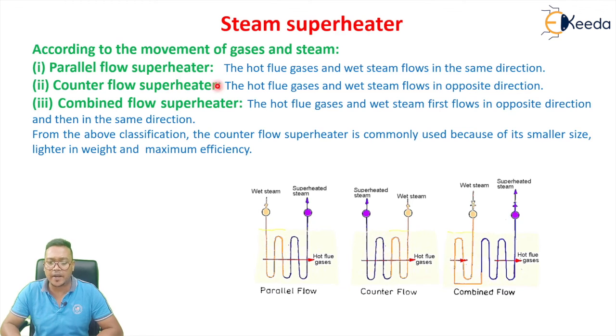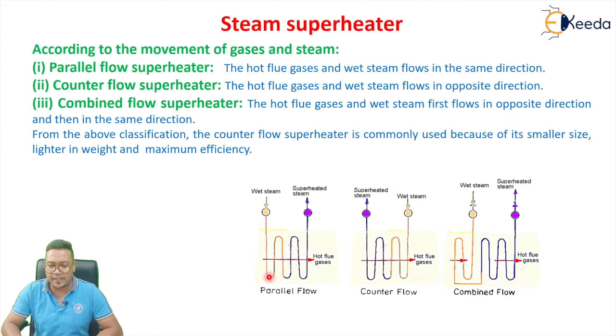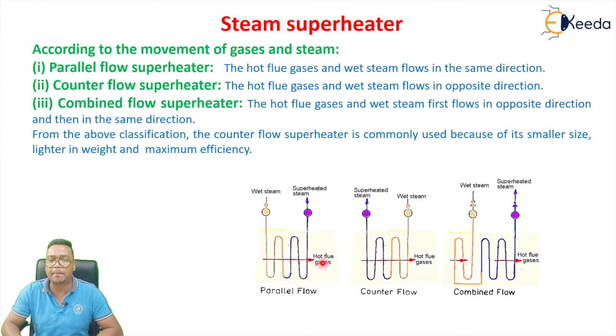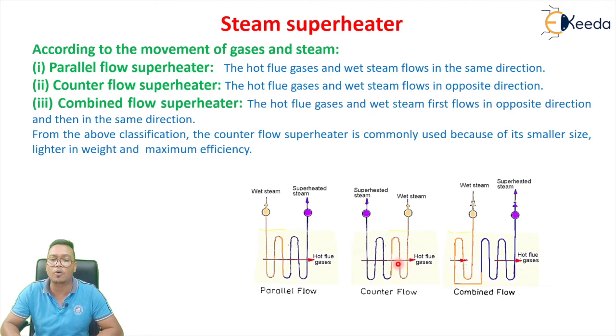According to the movement of gas and steam, superheaters are classified as: parallel flow — where wet steam and hot flue gas both flow in the same direction; counter flow — where flue gas flows in one direction and steam flows in the opposite direction; and combined type — where both parallel and counter flow arrangements are present.